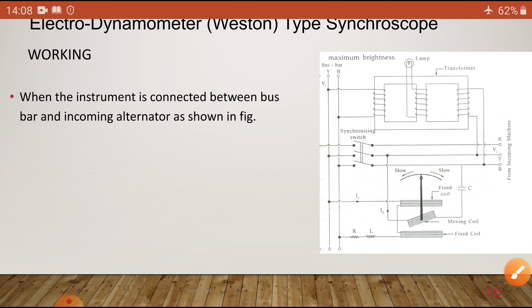The working: when the voltages of the two primaries are in phase - so here both, this is the primary, this is the primary, this is the secondary - V1 and V2 are both voltages. When the voltages of the two primaries are in phase, the two primary fluxes in the central limb are additive. Flux phi 1 and flux phi 2 are additive, so resultant phi r equals phi 1 plus phi 2 as a vector sum.